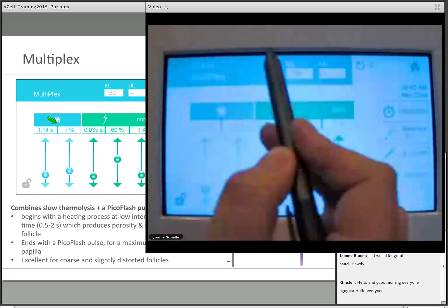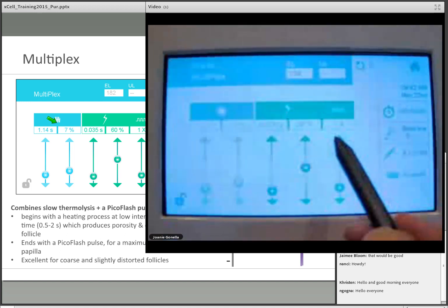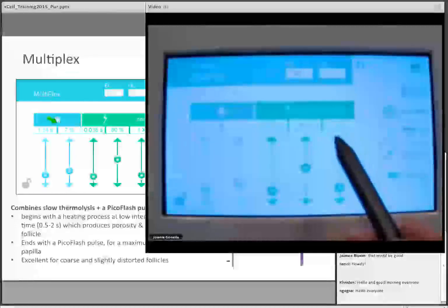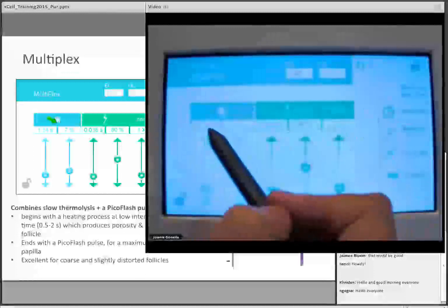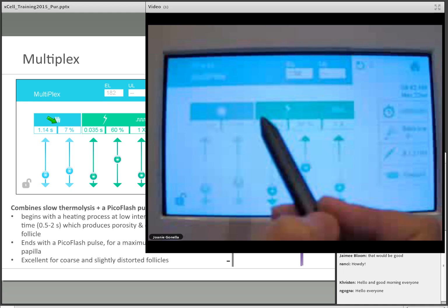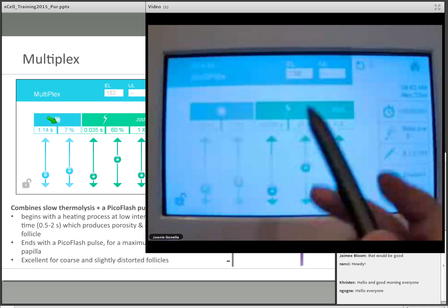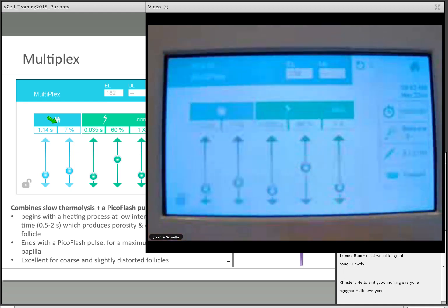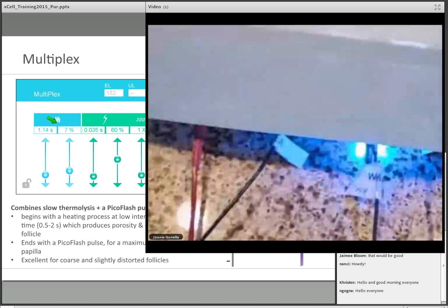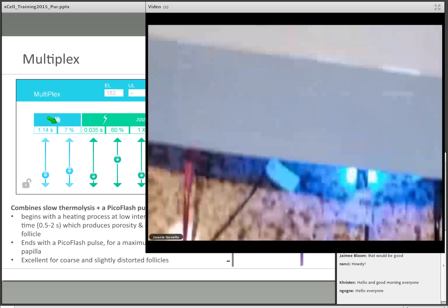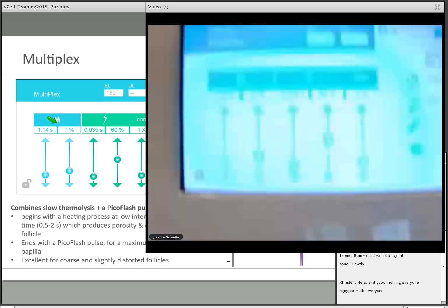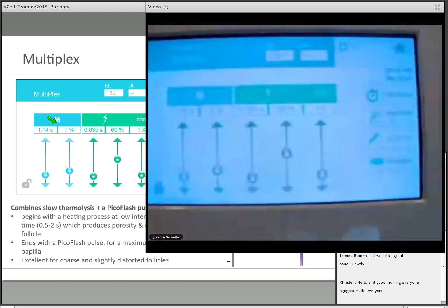It just got rid of my second pulse. Again, if I want to do 2 pulses, I'll have to set it up here. With this setting here, I have 1.14 seconds, 7%, and then plus my Picoflash pulse. If I'm ready to work, I'll lock my padlock. Locking the padlock also lights up the probe holders that I will be using. And so make sure that you are on the correct probe cord. That's always the first thing to check when the current doesn't seem to be going through.